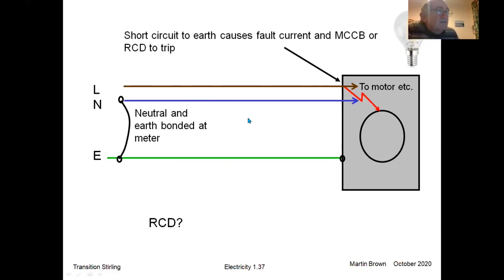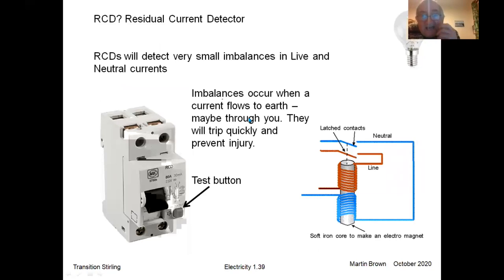So what's an RCD? Well, it's a residual current detector. It's detecting the imbalance in the currents between the live and the neutral. And again, you've got sort of an electromagnet, but now you've got a live coil and a neutral coil. As long as these two are balanced, there's no magnetic field. But as soon as we get a short circuit to earth, this magnetic field suddenly appears and opens the contact. So here's our RCD. It's a bit more complicated inside than an MCCB, and it's even got a test button to make sure that it's working, because it's a safety unit.